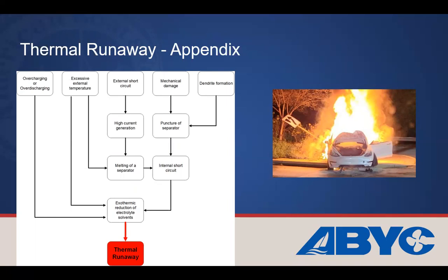And really, once you get into thermal runaway, it's a self-propagating heating condition that can occur within the cell or cells. A lot of times, once it starts in one cell, it starts spreading and spreading. And that's the problem: it's creating its own oxygen source and its own fuel source at this point. So as soon as you have enough heat to auto ignite, that's when bad things happen.